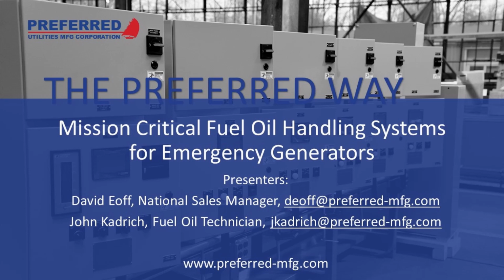Wow. So at the beginning of the presentation, I showed an energized to alarm circuit and had a list of things that can go wrong in an energized to alarm circuit, like a blown fuse, a broken wire, a terminal block not tightened down, a malicious rodent. I have personally seen all those things doing either boiler startups or fuel handling system startups. How about you? What's the weirdest failure you've seen in a fuel system?